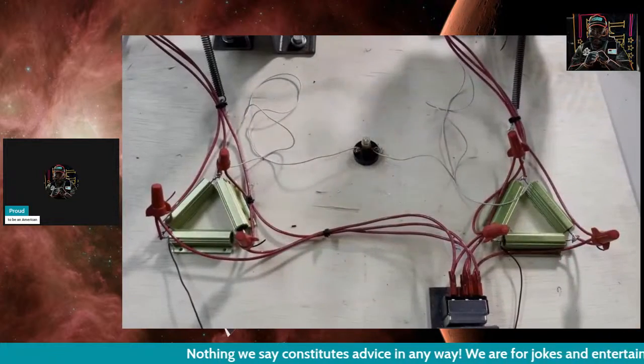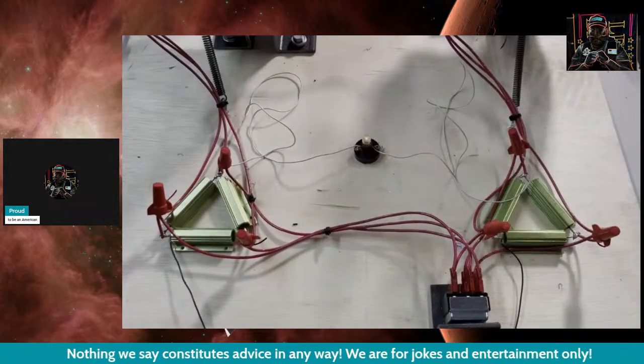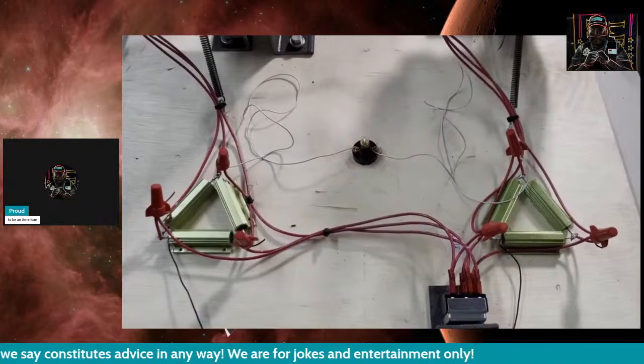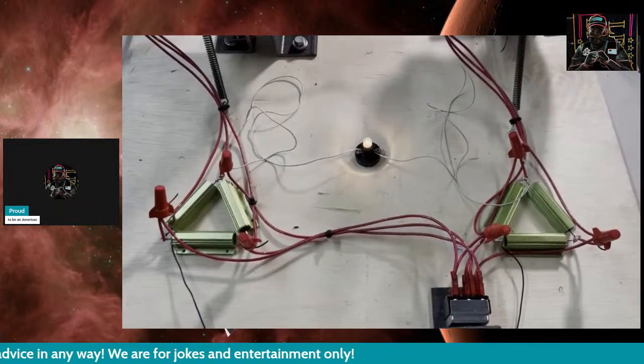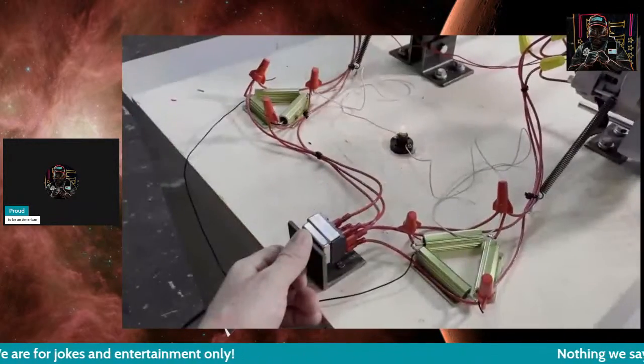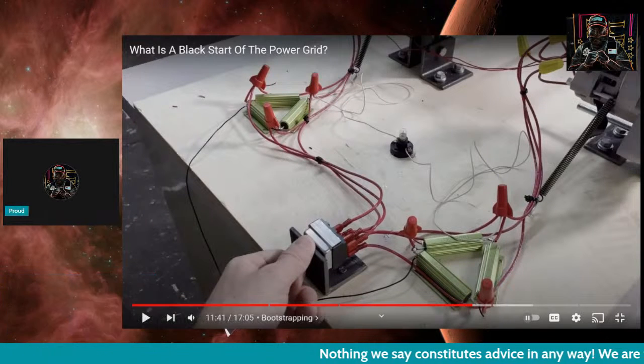One way to check this is to simply connect a light between the same phase on the two grids. If the light comes on, you know there's a difference in voltage between them and they aren't synchronized. If the light goes off and stays off...